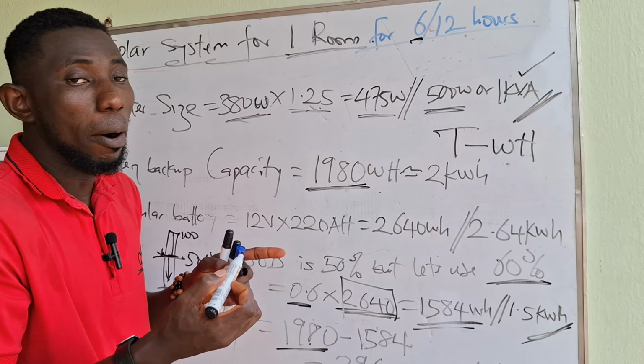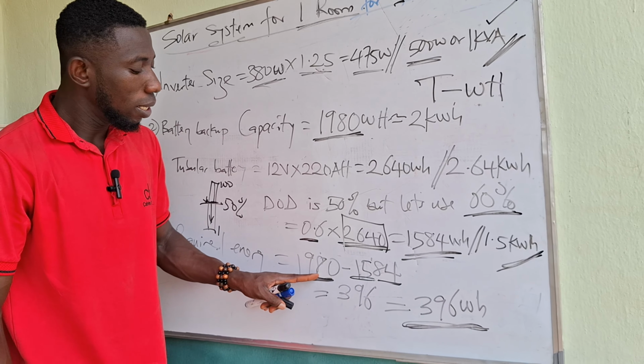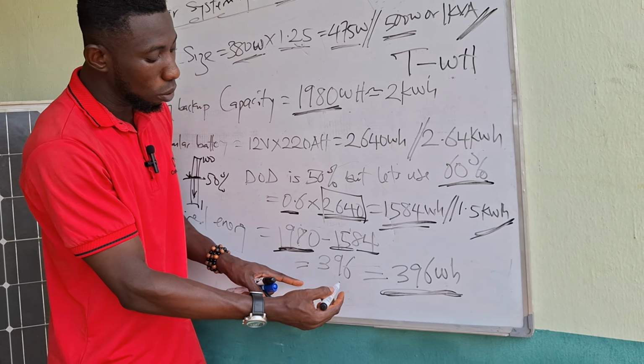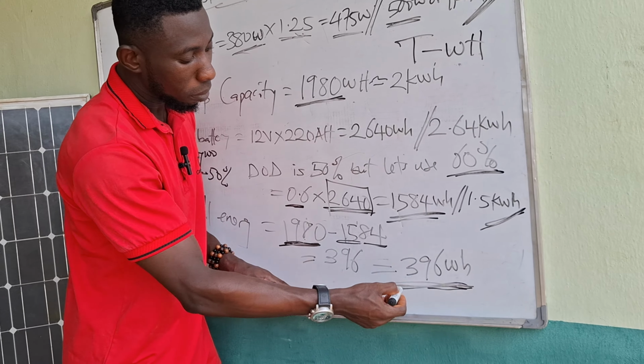If our total battery watt-hour is 1,980 watt-hour, and we calculated with our DOD using one tubular battery of 220 amps hour, it's giving us 1,584 watt-hour. If you minus this from that, it gives you 396 watt-hour. So we find out that the energy needed to power this load for 6 hours, in addition to that tubular battery, is 396 watt-hour.